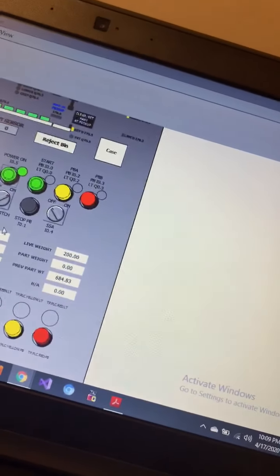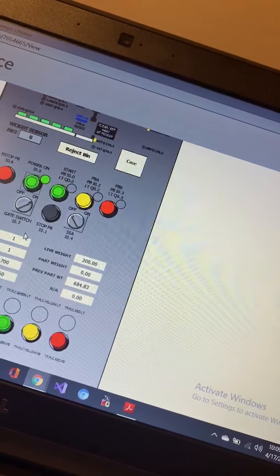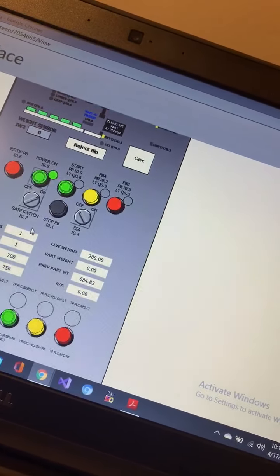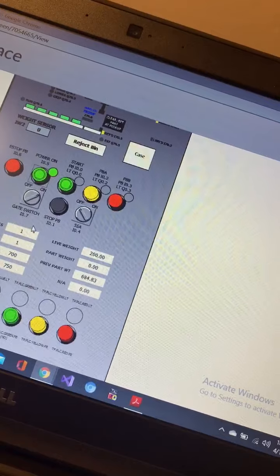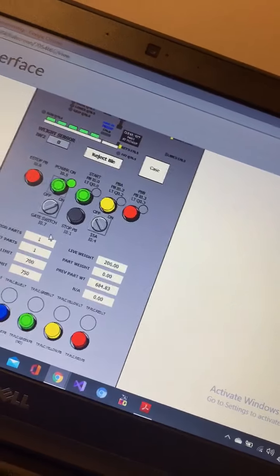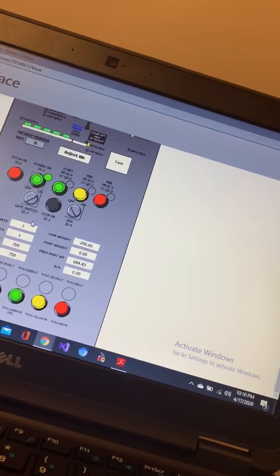So in my weight check station control function, I calculate the weight, and I made a formula to calculate the weight of the part. So part timer, when weight is done, move to real 3 and previous weight is shifted to real 2. I used a move and one shot instruction in that network. So when the part is between the lower and upper limit, the yellow light will turn on. So in out of range, when the part weight is not between the lower and upper limit, the red light will turn on.